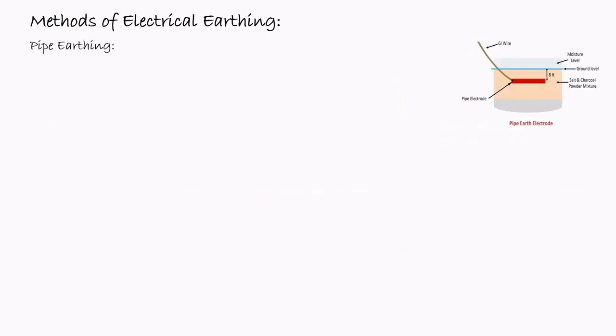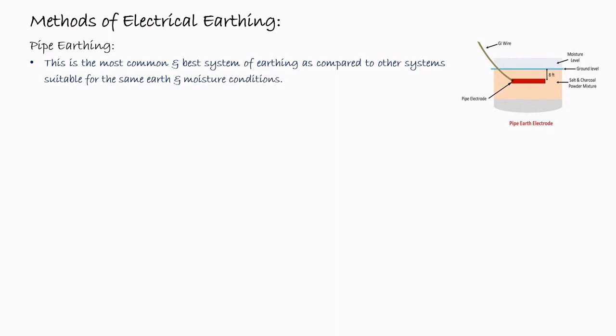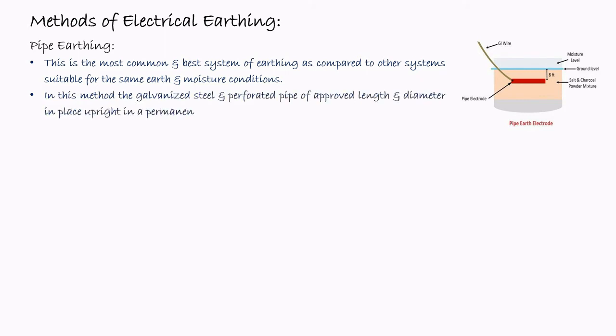Next is the pipe earthing method. This is the most common and best system of earthing compared to the other systems, suitable for the same earth and moisture conditions. Here in this figure we can see the pipe electrode placed around 8 feet below the ground, and here is the moisture level, that means the wet soil is here, and the GI wire is connected to this pipe as an earthing wire. In this method, a galvanized steel or perforated pipe of approved length and diameter is placed upright in the permanently wet soil, as shown in this figure.